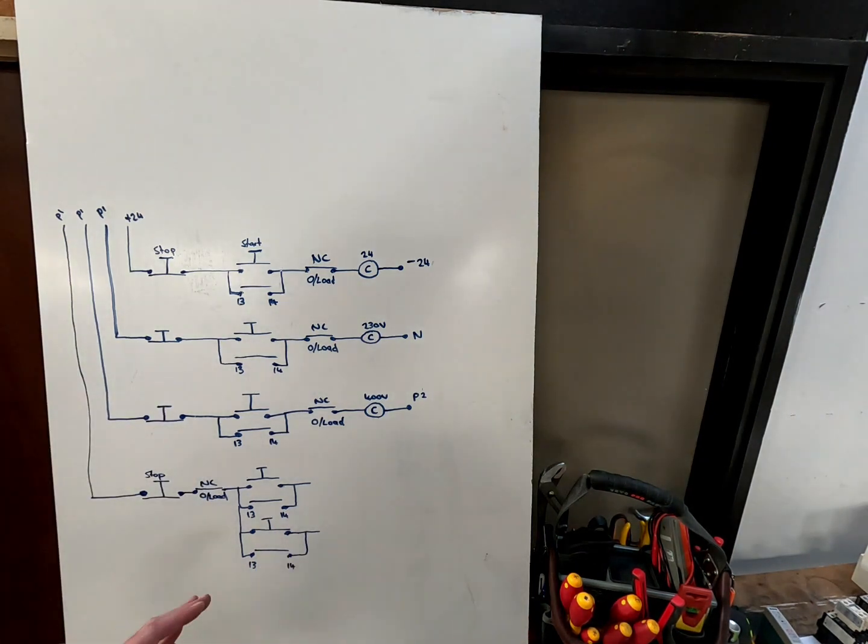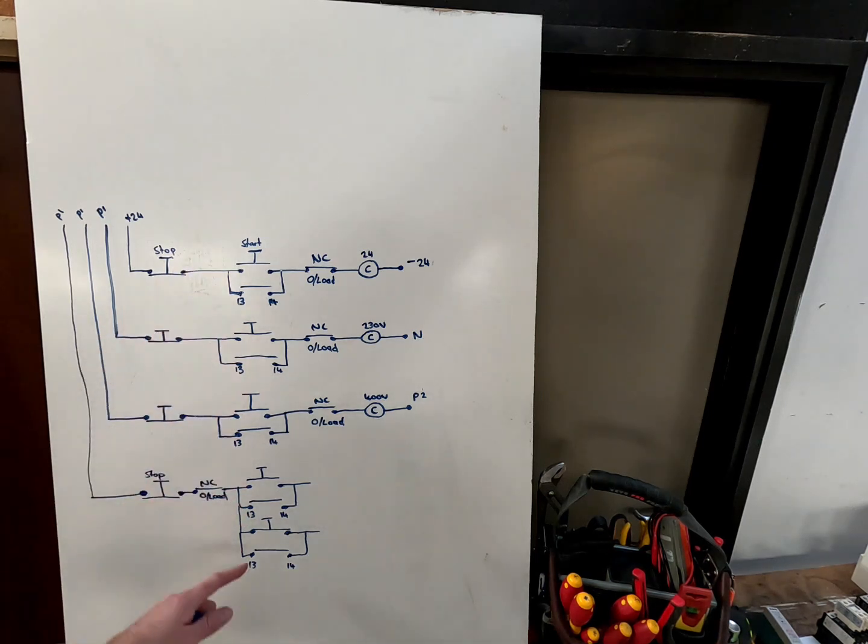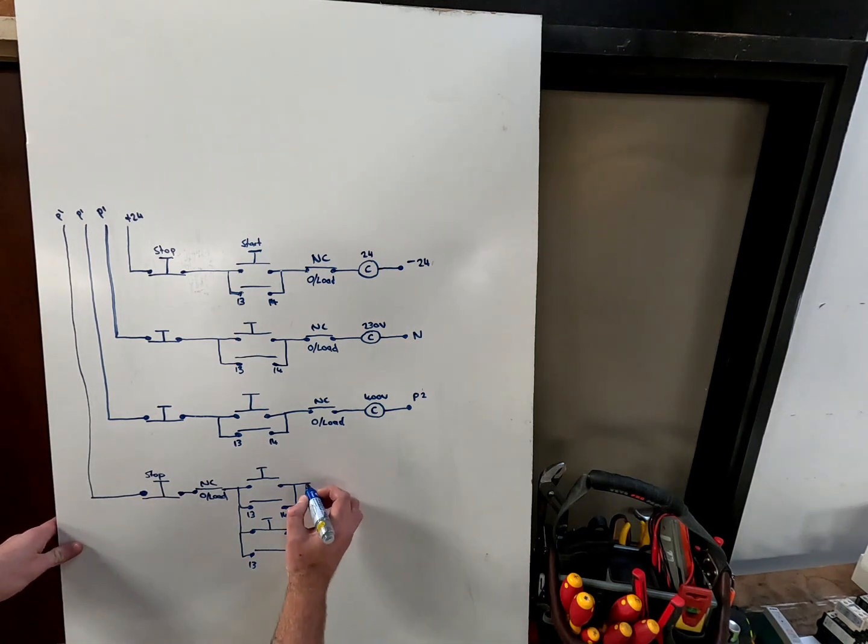Currently the way we have it is if you press this button, obviously power will carry on here and it will hold in this contactor, just like normal and same here. The only difference between this one and this one is this one will just have the three phases differently so that the motor goes the opposite way.